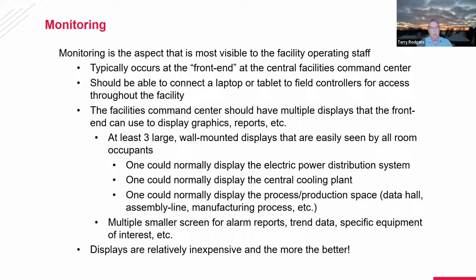The command center should have, in my mind, as many displays as you can get in the room, basically. Today, displays are fairly inexpensive. The more information you can put up on the screens, the more information is then available to your staff, especially during an anomaly situation. Typically what I've seen is a minimum of 3 large screens and then a series of smaller ones. One screen could have the electric power, one the cooling plant, and one the area of interest, like a data center, computer room, or a factory assembly line, or a lab, whatever. And then you can use the multiple smaller screens to put alarm reports up, or to drill down to a specific piece of equipment, or for whatever you might need.